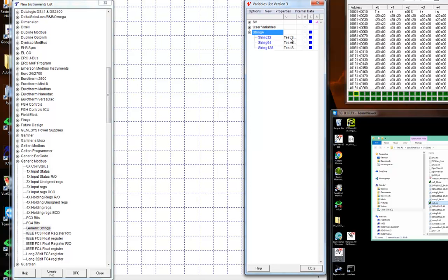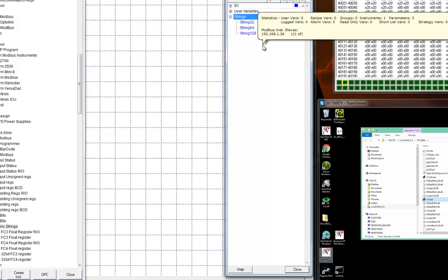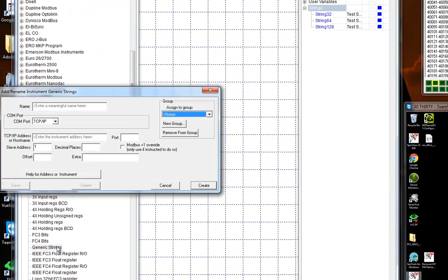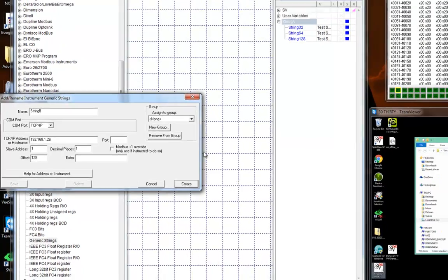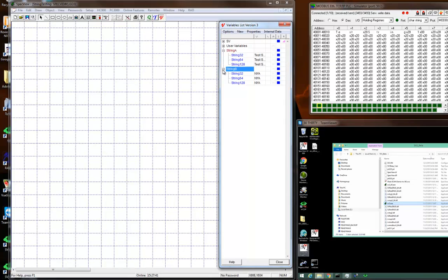There's already something in it that I was playing with earlier — we'll come back to that in a minute. If you want another string, you have to use a different offset so that it appears in a different place. Since the biggest string in here can be 128 bytes, I'm going to create one with an offset of 128. So here is String B, same address 192.168.1.26, slave address 1, one decimal place, now an offset of 128. Create.